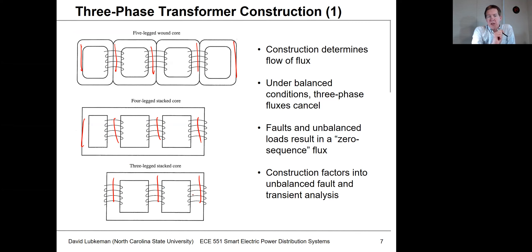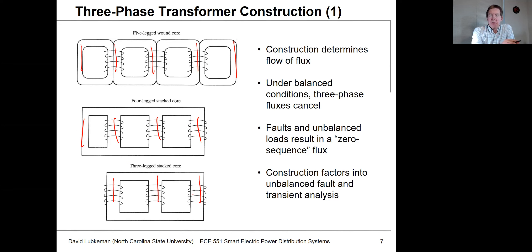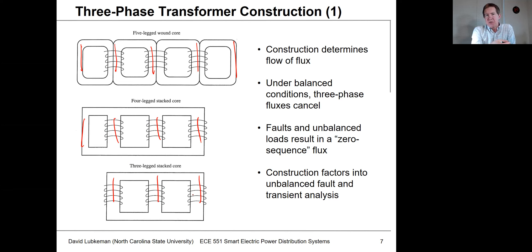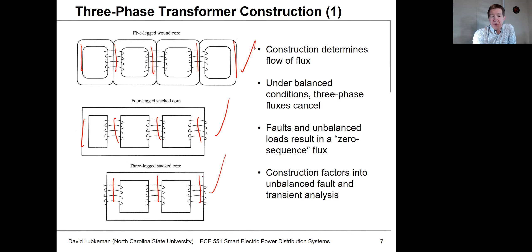In these three core types, we get different flux flows during imbalanced conditions. Under balanced conditions, the A, B, and C phase fluxes tend to cancel each other out and the core type doesn't matter as much. But with unbalanced currents, you get imbalanced flux in the core, giving different effective impedances for the zero sequence. This matters for fault analysis — whether you have a five-legged, four-legged, or three-legged core. For our voltage drop calculations in this class, it won't make a difference.